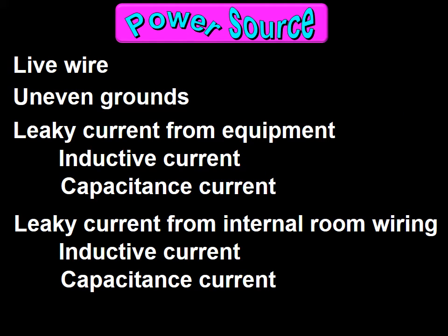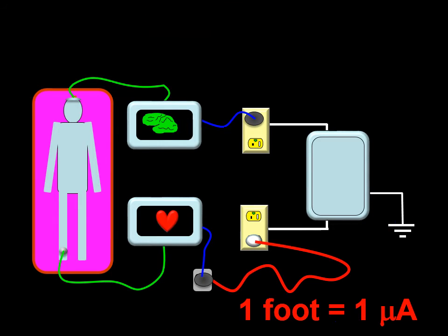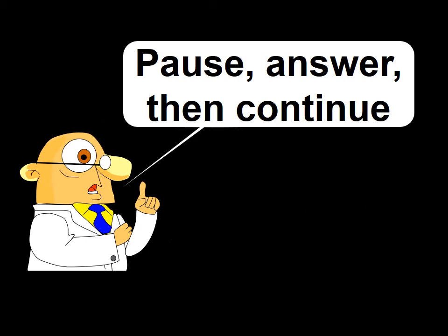The final example I will give regarding power sources is the generation of leaky current as a consequence of extension cords. It is estimated that one foot of extension cord, while conducting the usual alternating current of 60 Hz and 120 volts, will produce one microamp of current per foot. Hence extension cords are bad because they may produce unequal grounds, thus generating voltage imbalance, and also because they themselves produce leaky currents. At this point I will end the conversational section of this talk and switch to the question and answer format.